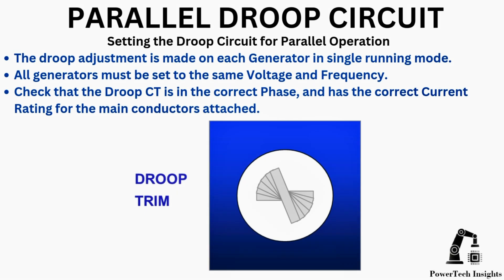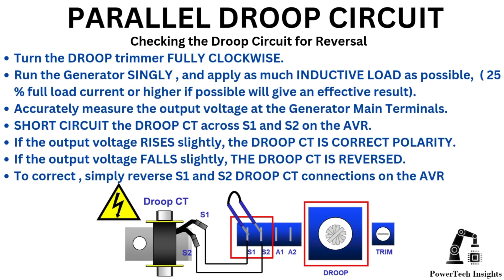Setting the droop circuit for parallel operation: the droop adjustment is made on each generator in single running mode. All generators must be set to the same voltage and frequency. Check that the droop CT is in the correct phase and has the correct current rating for the main conductors attached. To check droop circuit for reversal, turn the droop trimmer fully clockwise. Run the generator singly and apply as much inductive load as possible — 25% full load current or higher if possible will give an effective result. Accurately measure the output voltage at the generator main terminals. Short circuit the droop CT across S1 and S2 on the AVR. If the output voltage rises slightly, the droop CT is correct polarity. If the output voltage falls slightly, the droop CT is reversed. To correct, simply reverse the S1 and S2 droop CT connections on the AVR.